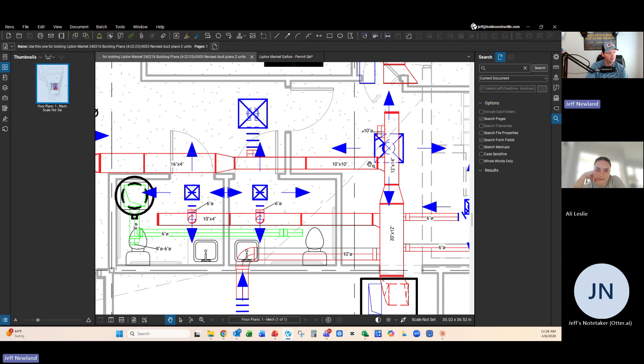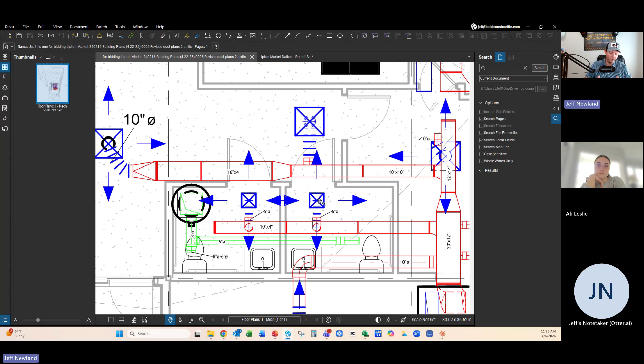We were actually able to size all of this down. Think about ductwork as moving air, that's what you're moving. So say a duct calls for it to be 30 by 30, something like that, but you've only got a 24-inch space to run it in, so that's not going to work. You could go back to your HVAC contractor and say, here's our problem: we've got trusses with a very small space, and with your ductwork and insulation, because they have to insulate the ductwork, that adds like an extra 2 inches on each side. So if it called for a 30 by 30, we're actually going to be at like 34 by 34. He should be able to look at that, and it could also be done via RFI.